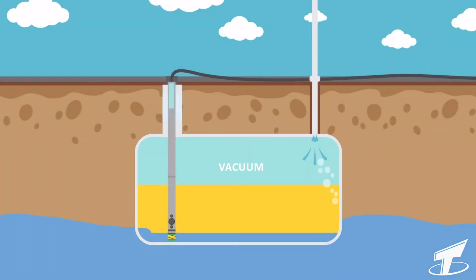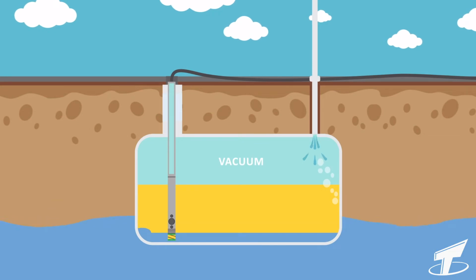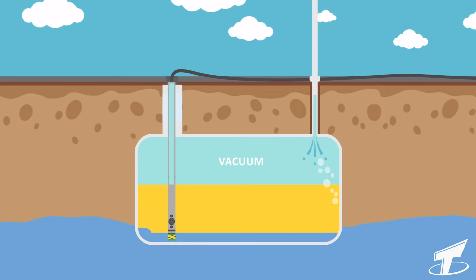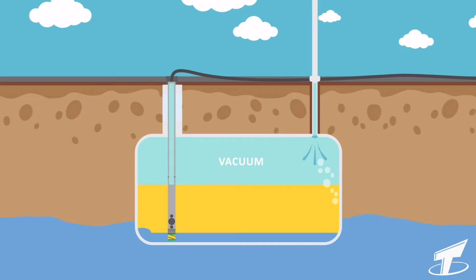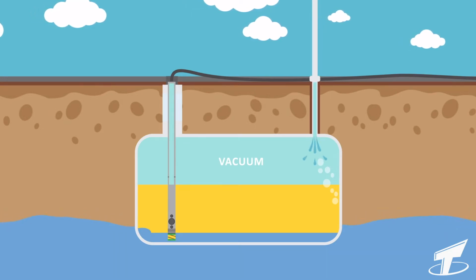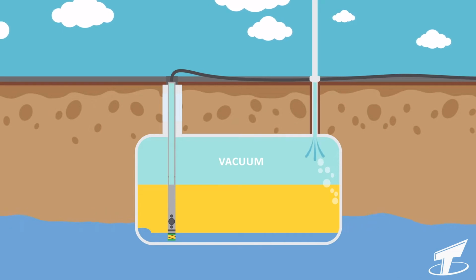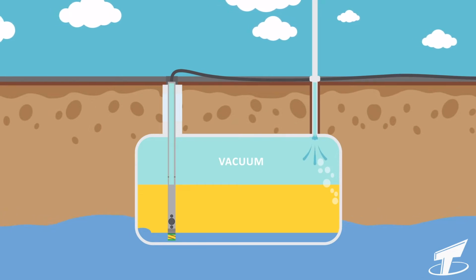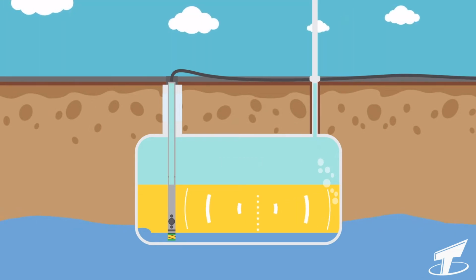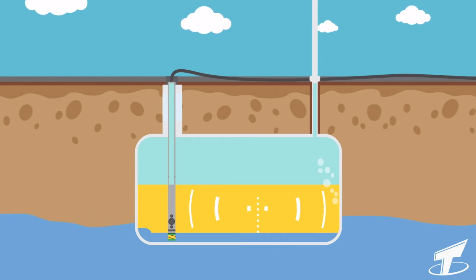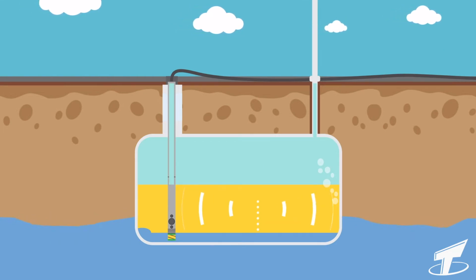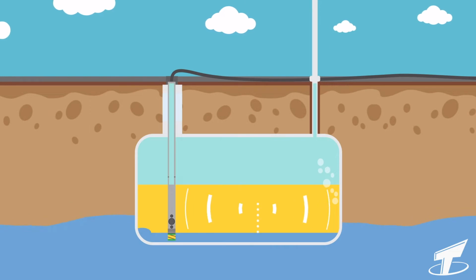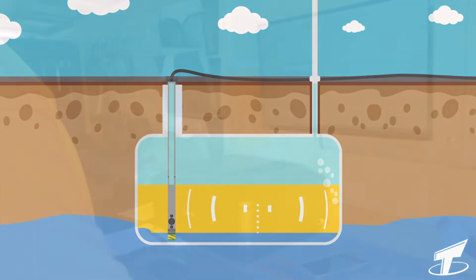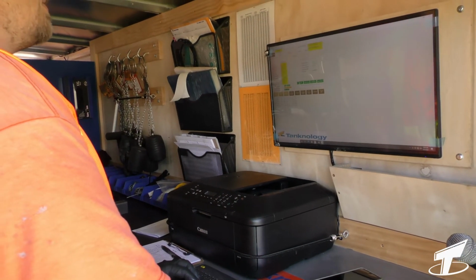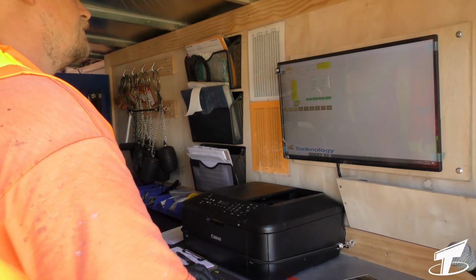An explosion-proof vacuum pump produces a slight vacuum, enough to ensure that the entire inner surface of the tank has a negative pressure relative to the outside of the tank. This negative pressure will draw water or air into the tank through any leak or any other opening. Any air that enters below the product line will create a unique bubble signature in the tank's liquid. This generates a pulse frequency that is detected by the probe and recorded by the VacuTect technician, who is trained to recognize the bubble signatures.